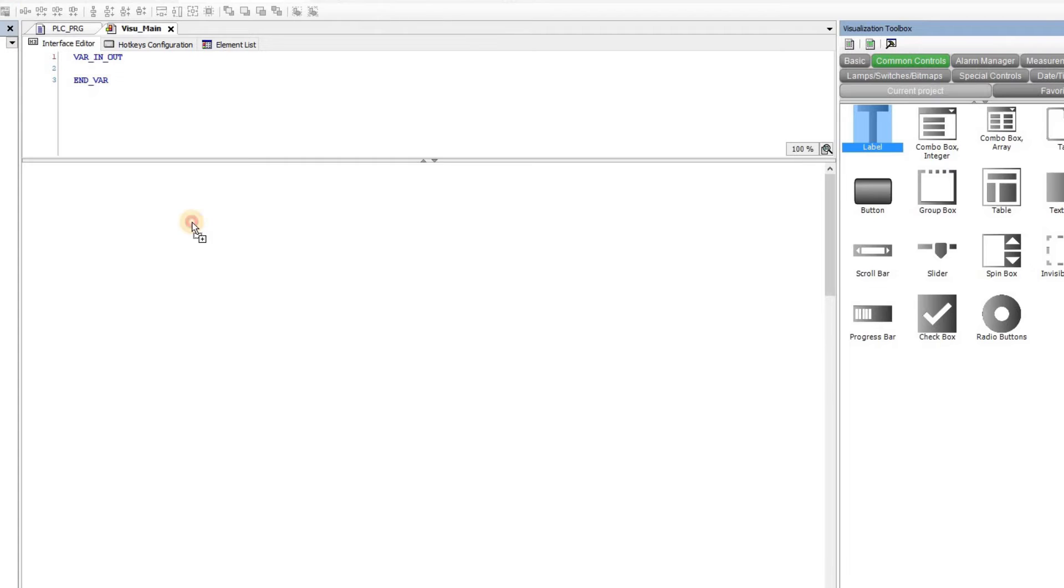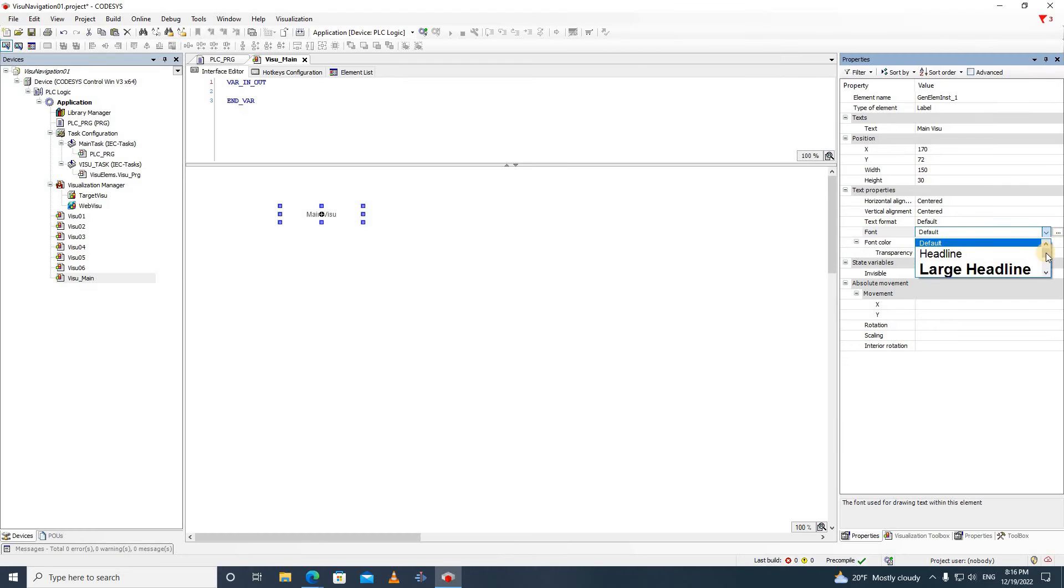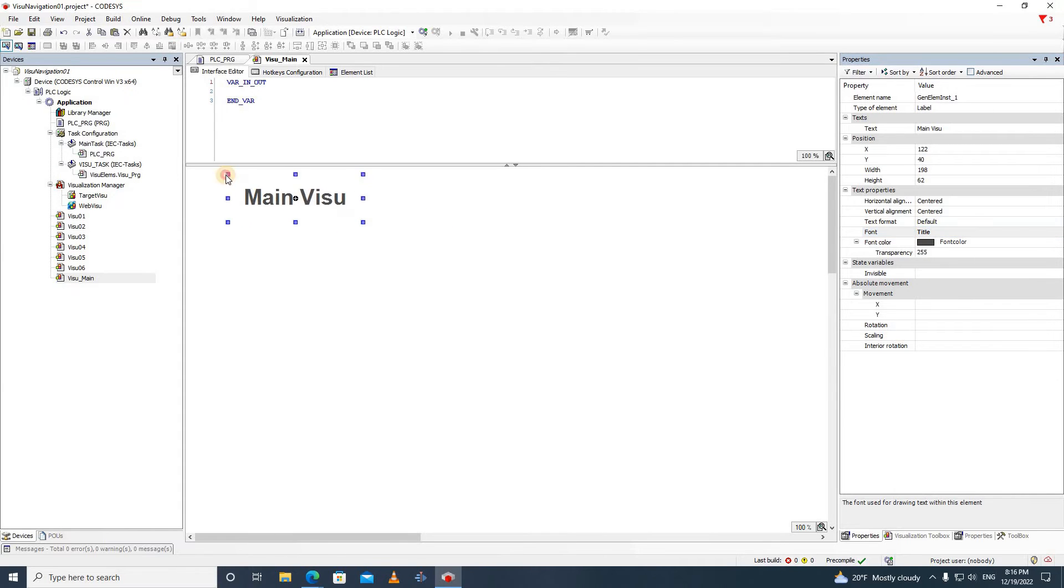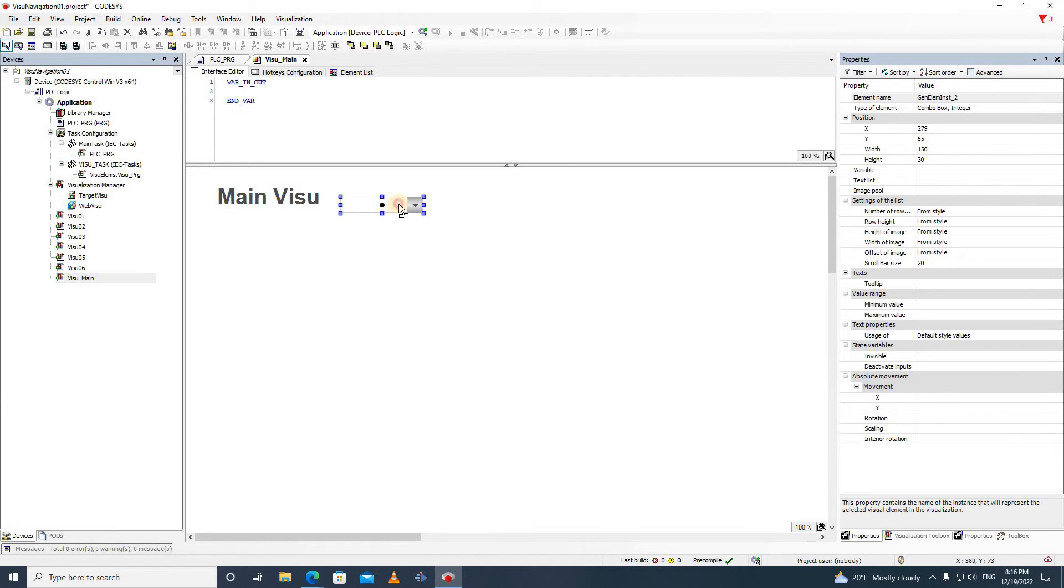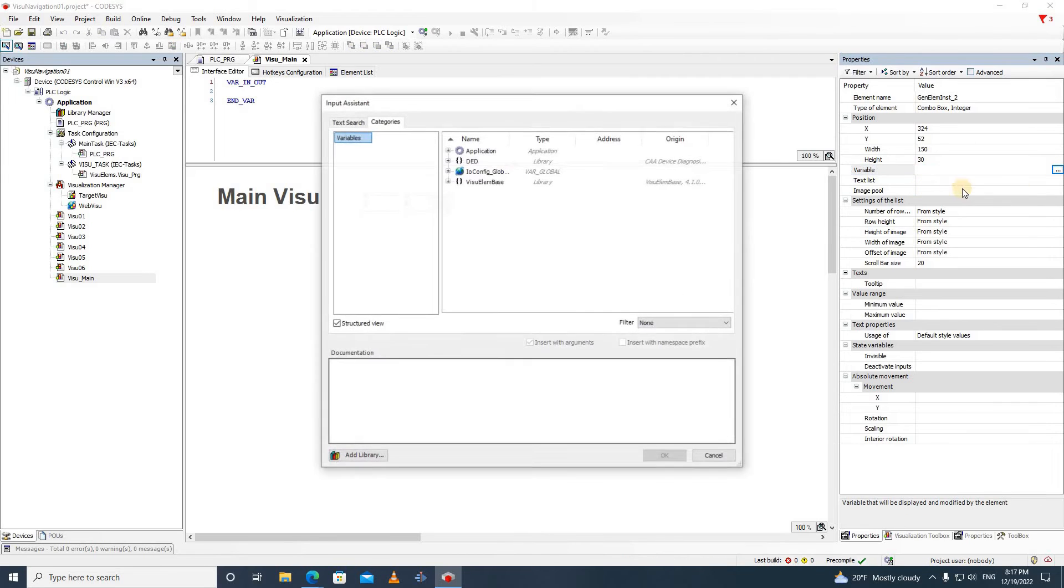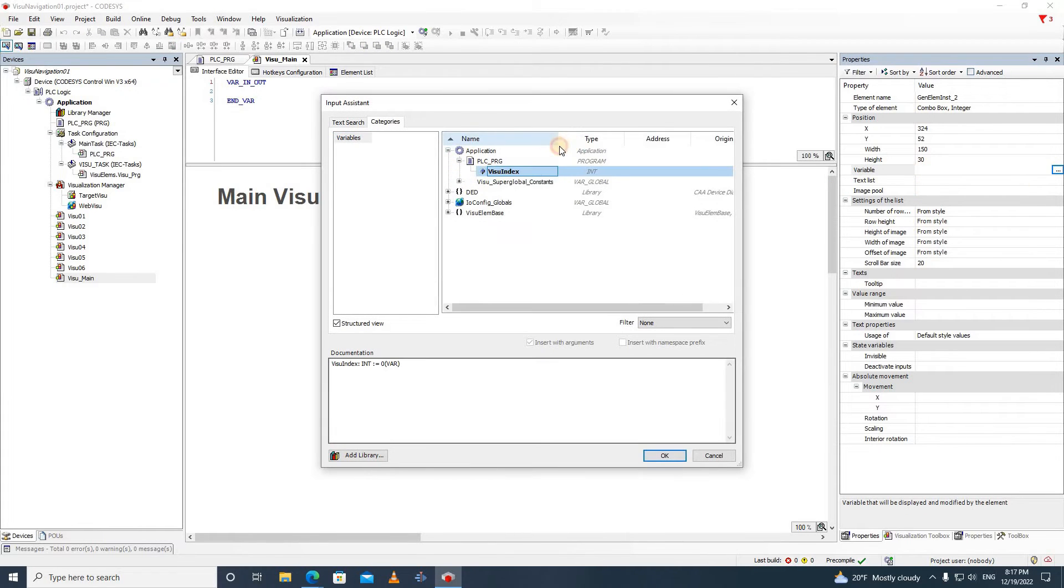In the main visualization window, I have inserted the label and used mainVisu as the text to distinguish a widget from all the other visualization windows. Then I have added a combo box integer element. As for the variable, I have chosen VisuIndex variable from PLC_PRG.